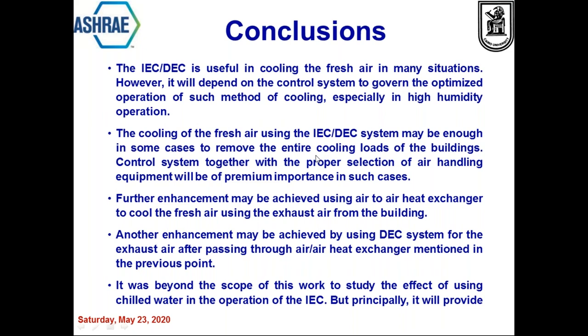It will be okay, and it will be okay for locations where we have masses, a large population of people, like in malls and places of assembly. Further enhancement can be achieved using the air-to-air exchanger to cool the fresh air using exhaust air from a building. Another enhancement may be achieved using a direct evaporative cooling system for exhaust air after passing through the air-to-air heat exchanger, as mentioned here. It was beyond the scope of this work to study the effect of using chilled water in the operation, but principally, it will provide better conditions.